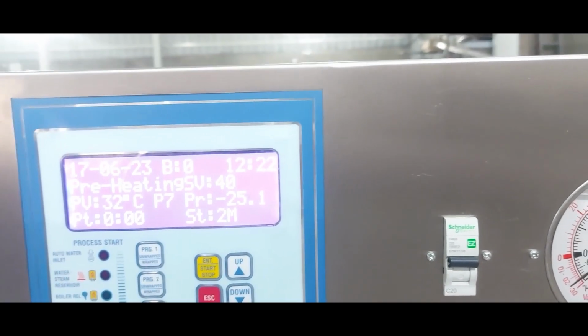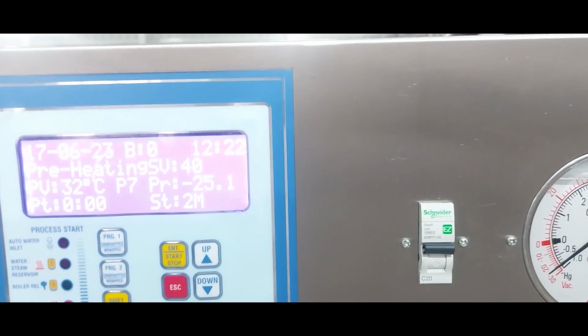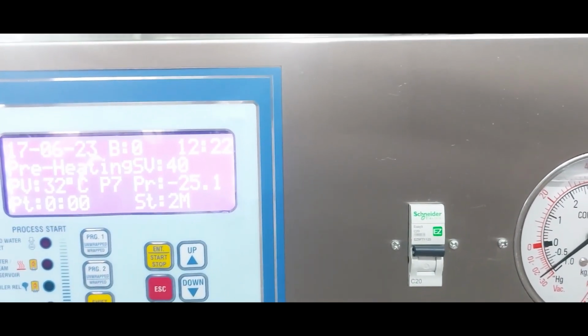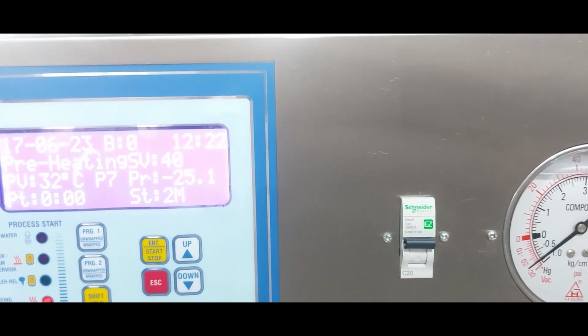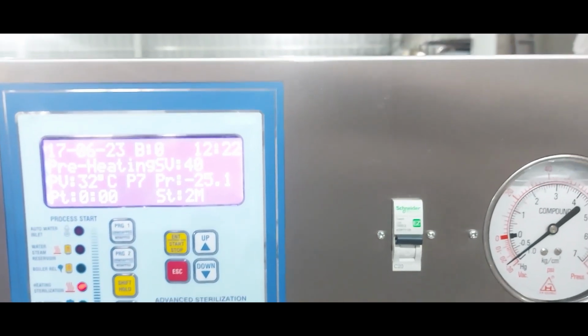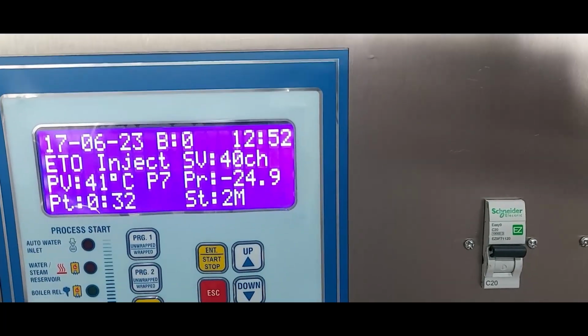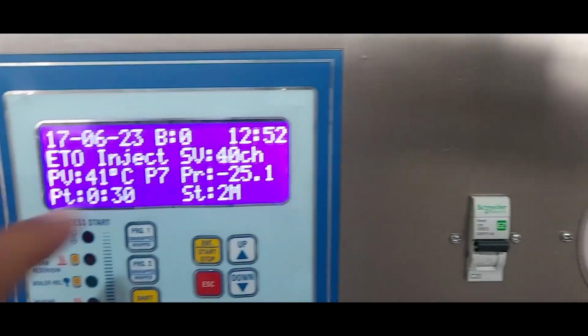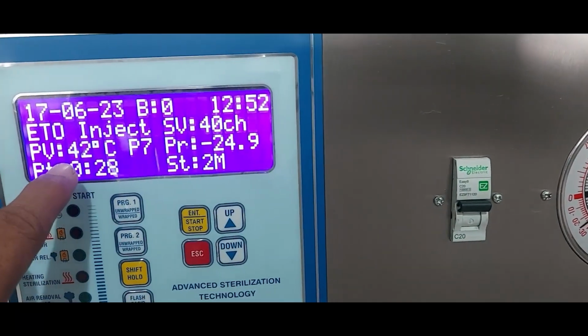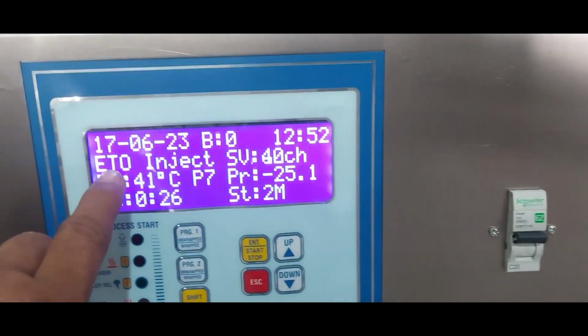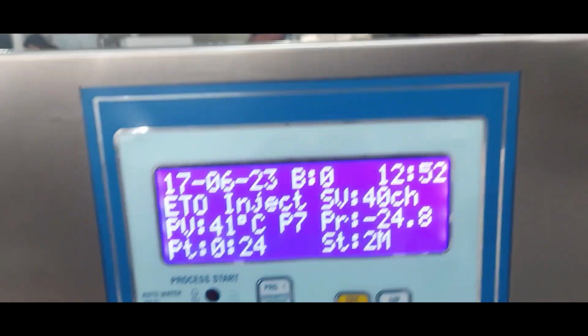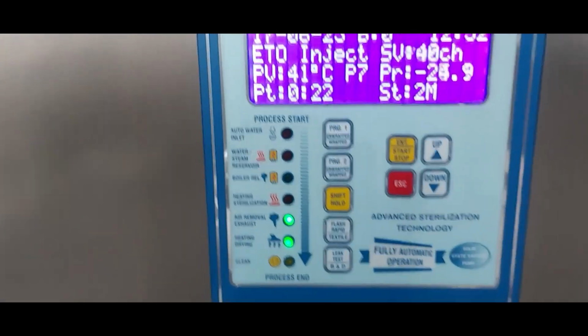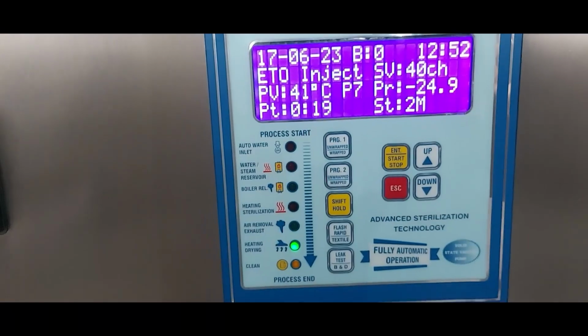We have used a silicone heater in the whole chamber to maintain a very uniform temperature across the system. Once the temperature reaches 40 degrees, the ETO injection starts. The ETO injection starts from this cycle. The solenoid will start firing.